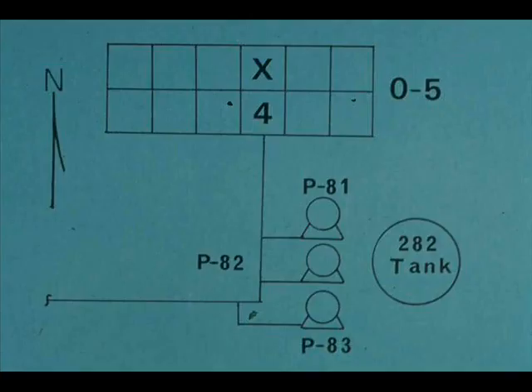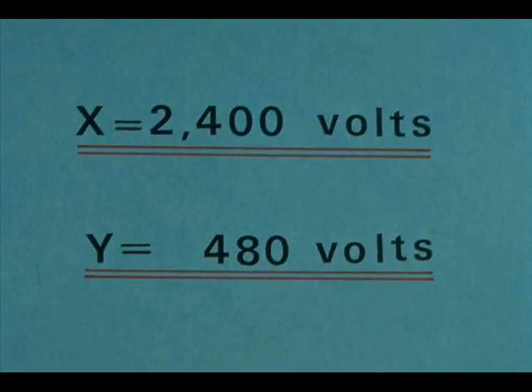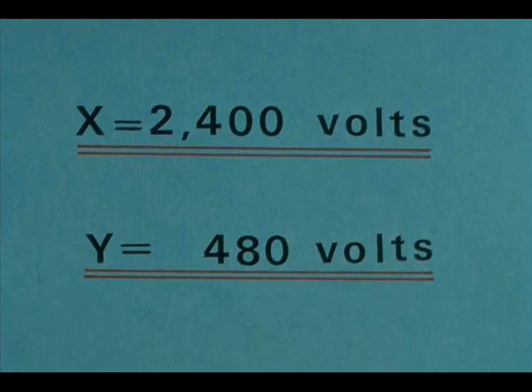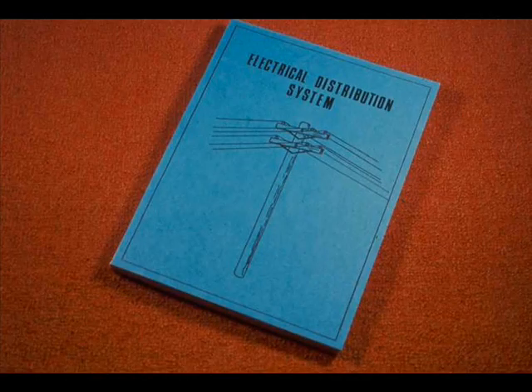Feeders from substations provide power for equipment. From O5 substation, for example, feeder X4 provides power for pumps numbers 81, 82, and 83, west of tank number 282. In one refinery, X means that the feeder carries 2,400 volts; Y indicates 480 volts. This description of an electrical distribution system is incomplete and nonspecific. It is important that you learn your plant system, especially those parts that serve your equipment.